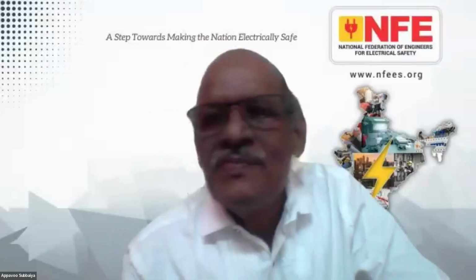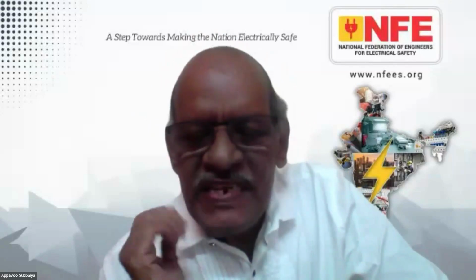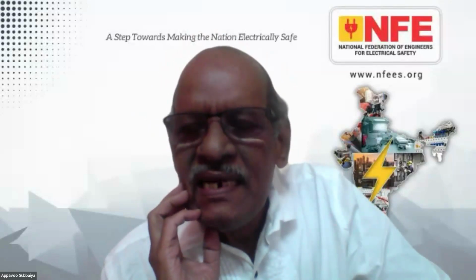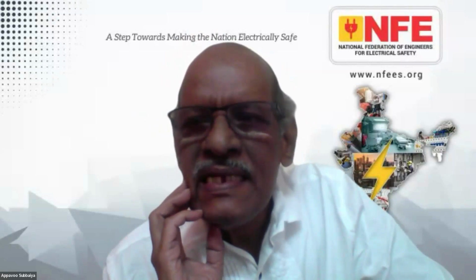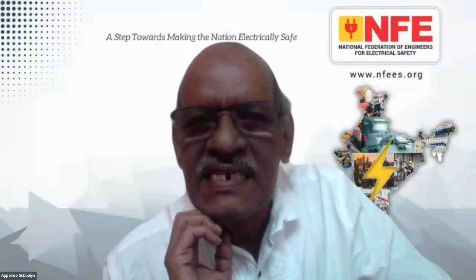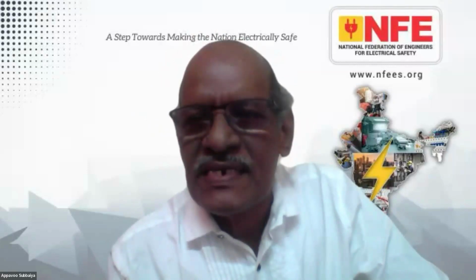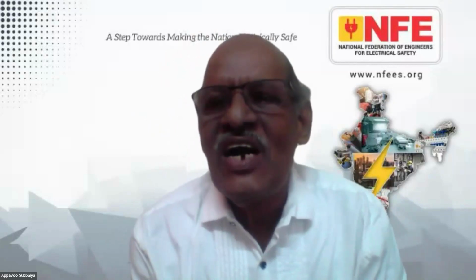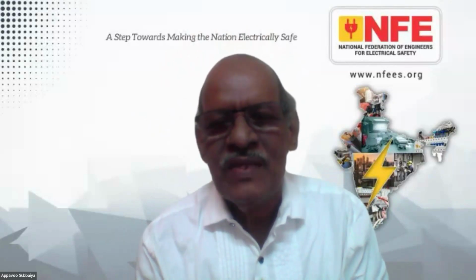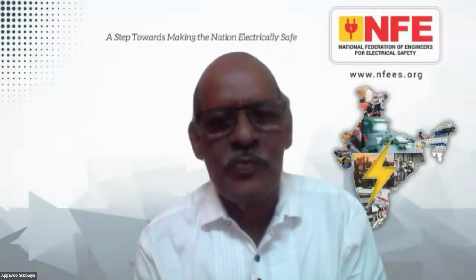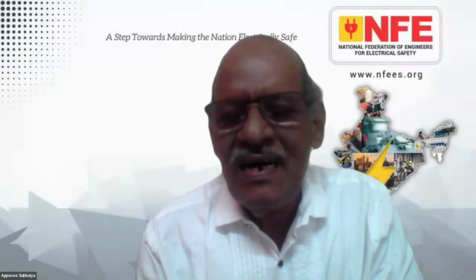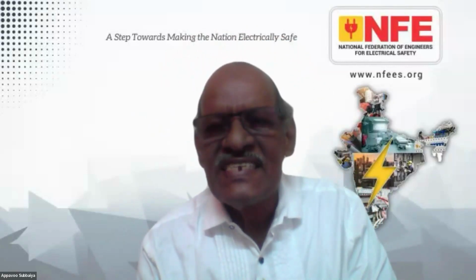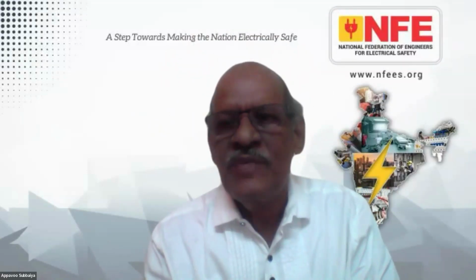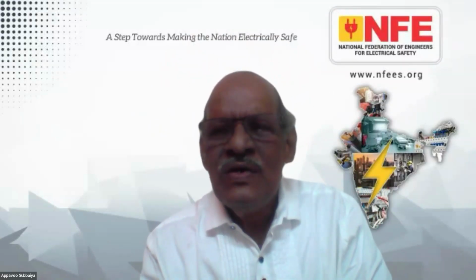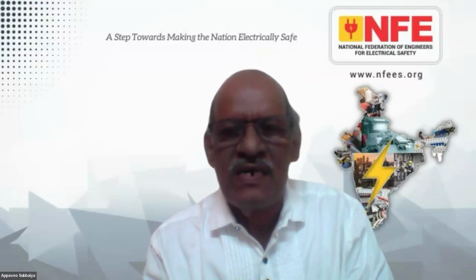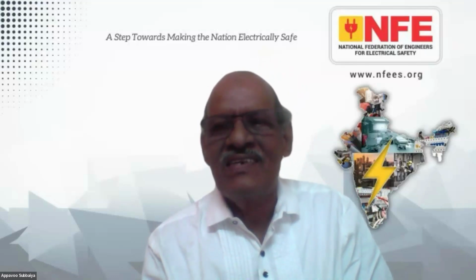Thank you, sir. Ms. Pallavi, there are specific forms available in the regulation, but they don't give all the parameters. You have to seek the verification measures that are all prescribed in the regulation that can be applicable. We can't have a common audit checkpoint - it may vary from installation to installation, for hazardous installations, swimming pools, community flats, or medical locations. There are specific provisions in the NEC for medical locations, so we have to verify those forms prescribed in the standards as well as the regulation. It's an art we have to evolve.